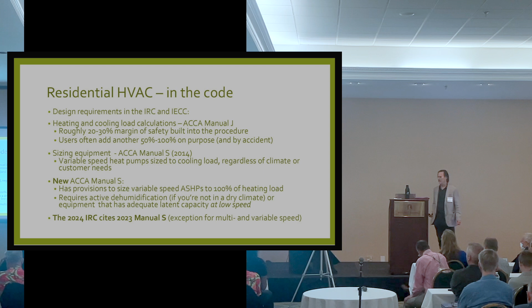There's a new edition of Manual S that was published at the end of last year, beginning of this year, and it actually has provisions for the first time to size variable speed heat pumps to 100% of the heating load. Let's give a round of applause to ACCA for doing that. Now, they also make it really, really complicated, because I think in order to produce any kind of a standards document, ACCA has to make something about as complicated as it can be.